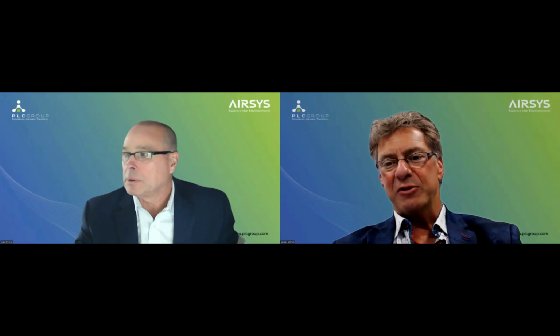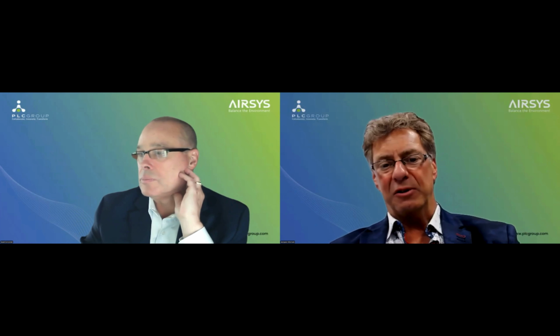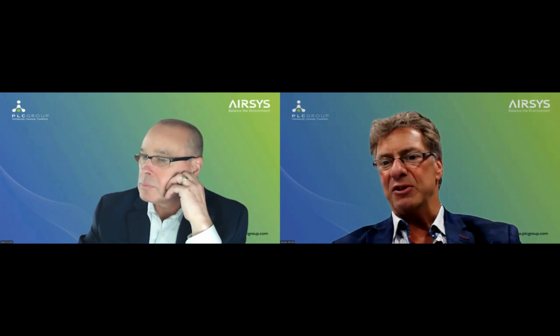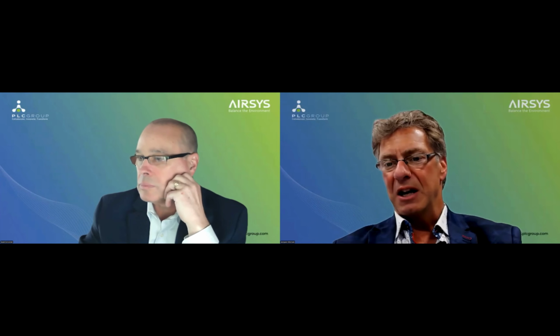On that same token, building a data center in a modular fashion allows you to have a higher PUE, because as your heat loads or IT load grow, you just keep adding more chillers or more batteries. It's completely modular. So you keep adding modules, and that maintains a high PUE, and you're not forecasting all the capital expenditure on a data center for IT loads you don't have yet, and maybe will in 5 years, but right now it's all capital spent for future loads. That's true, Jacques.